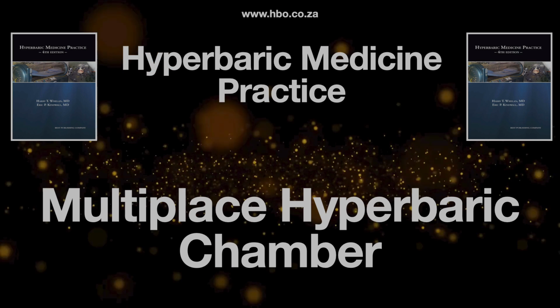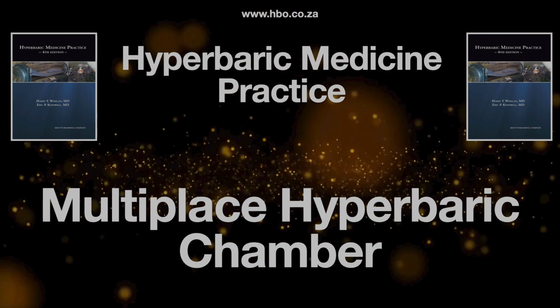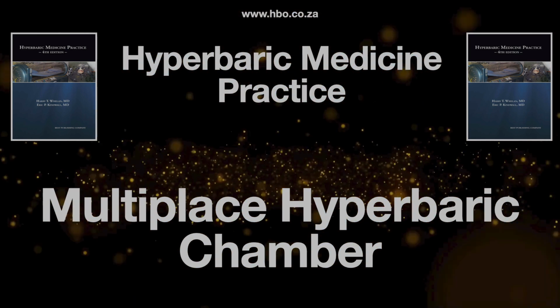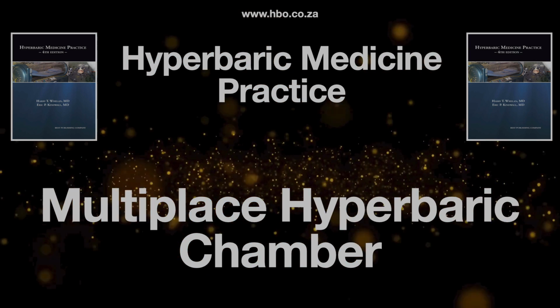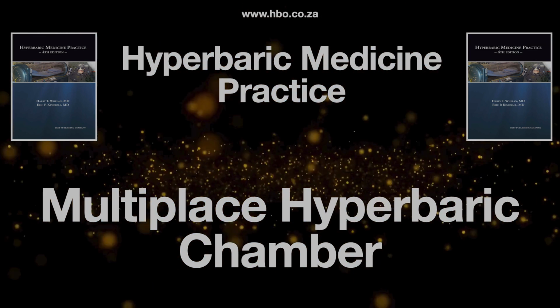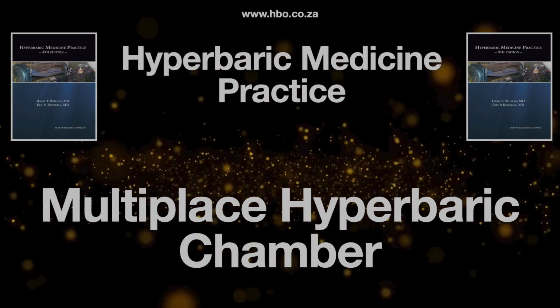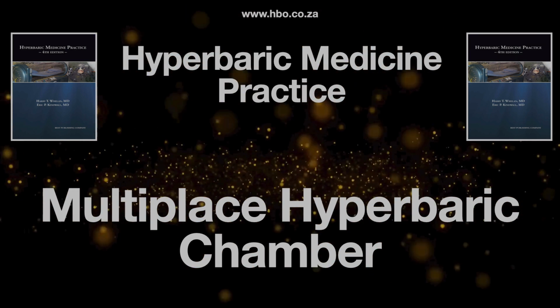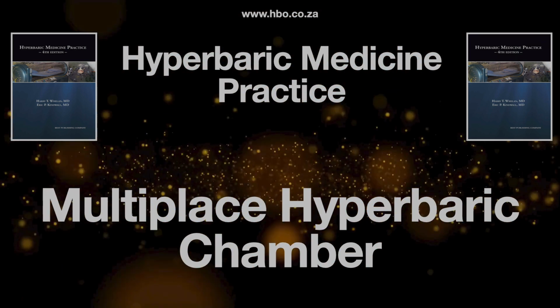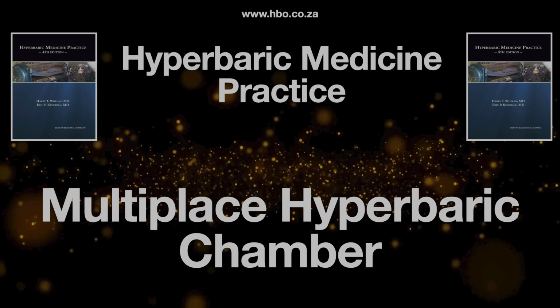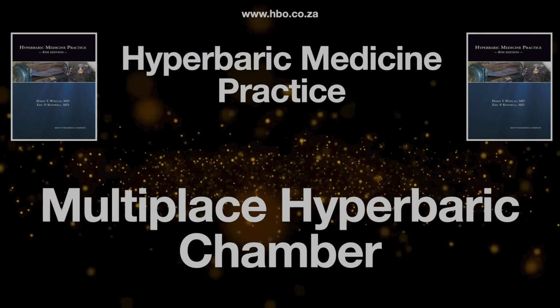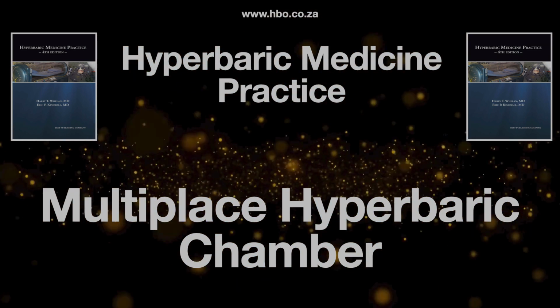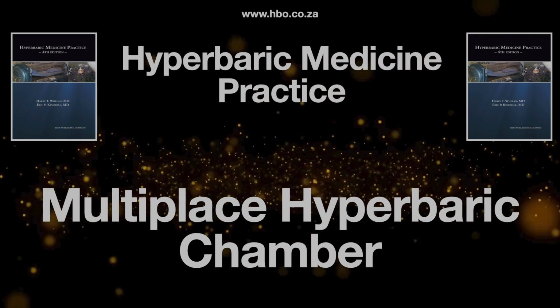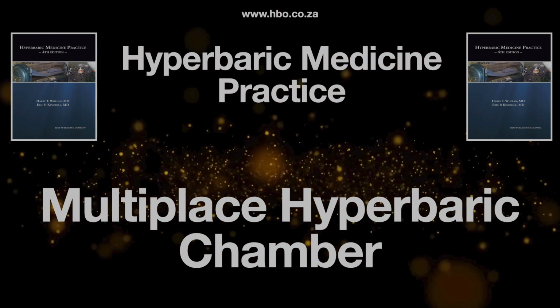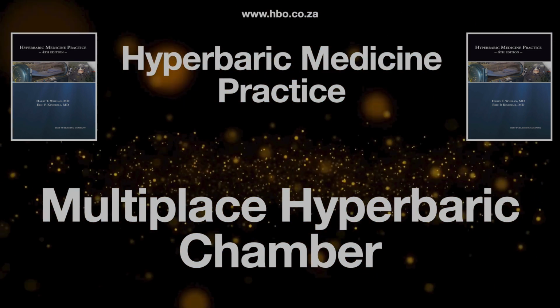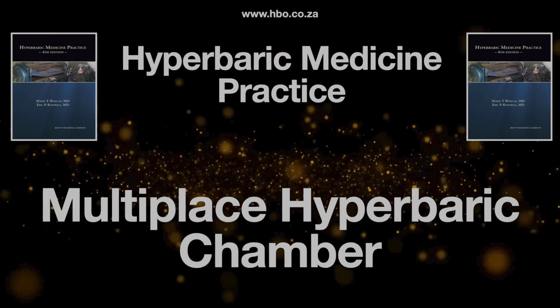Oh, yeah, absolutely. The systems for the main chamber and the airlock are separate and built with multiple safety layers, like you'd expect. Dual power supply for the air compressors, usually, with automatic and manual bypasses in case something fails. Got to keep that pressure stable. And the system needs to pump a lot of air, maybe 30 to 40 cubic meters per minute, to pressurize things reasonably quickly. Plus, they put silencers on the airlines. Why silencers? To cut down the noise inside the chamber. Makes it much more comfortable for the patients during the treatment. Good point. So it's a controlled, relatively quiet process.